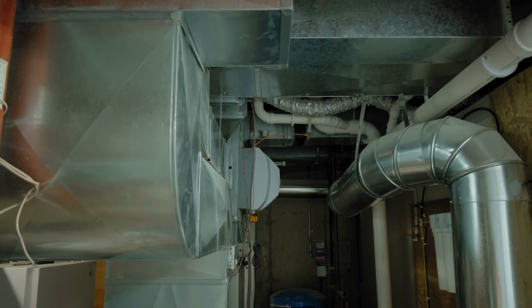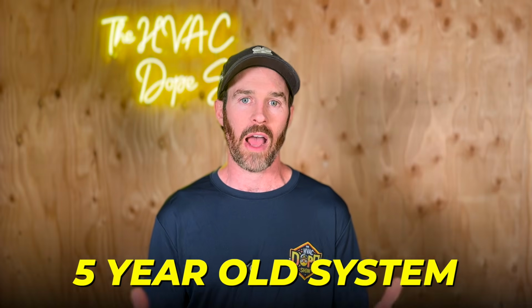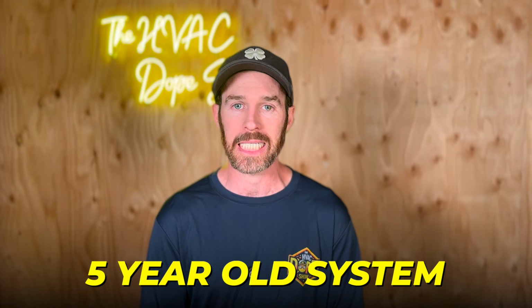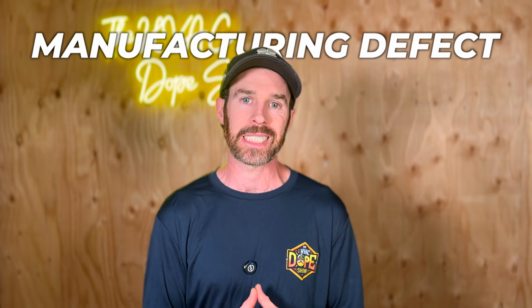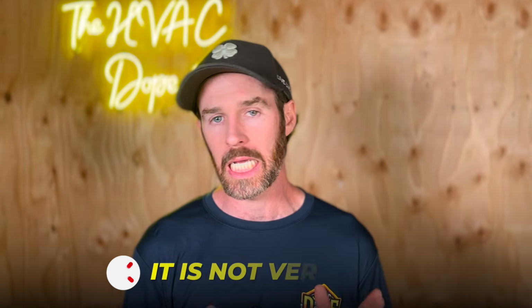Now, the exception to this is if you have a brand new system. Sometimes a system can develop a crack prematurely, or there was a manufacturing crack that developed just over time in a very short period of time. So if you have a 3 or a 5-year-old system and it happens to have a crack in the heat exchanger, on a newer system like that, they can replace the heat exchanger, and your new system does not need replacement because it's basically new and it was just either a manufacturing defect that developed. It's rare. We don't run across this often, but if we ever do, we know how to replace these heat exchangers because it does happen periodically. But again, it is not very common.